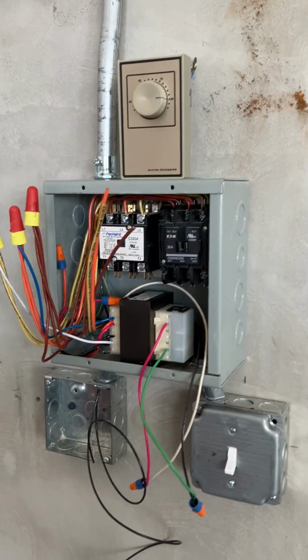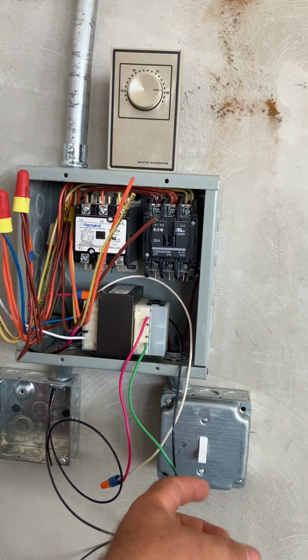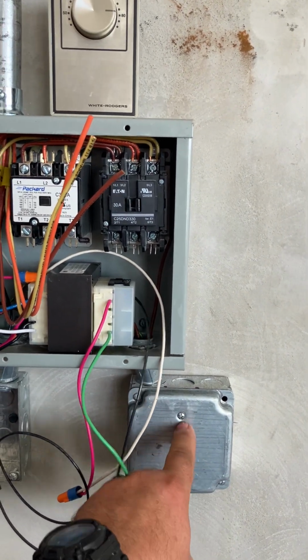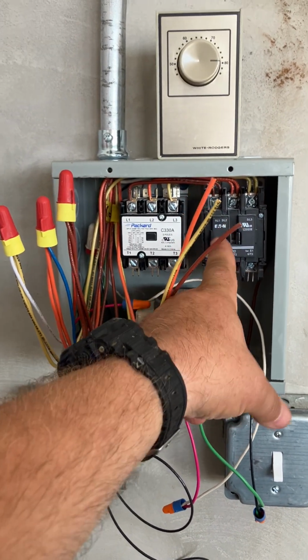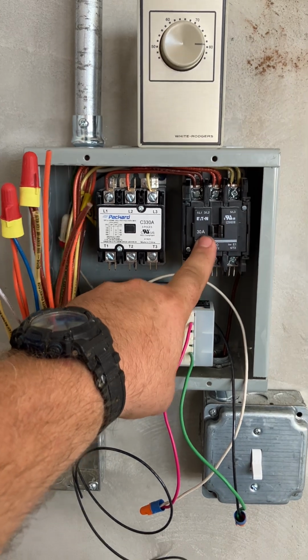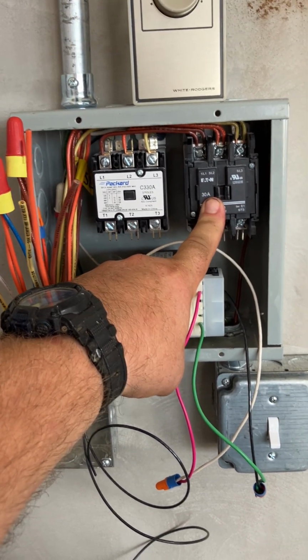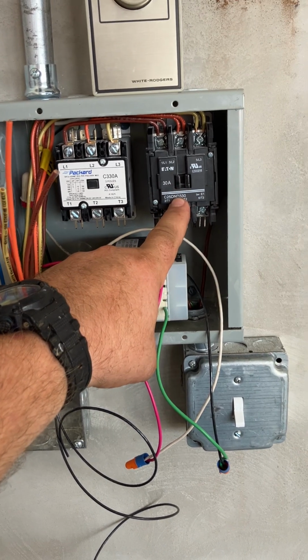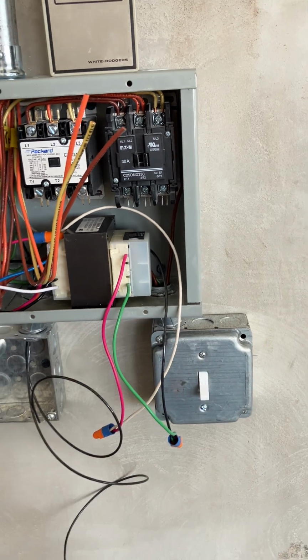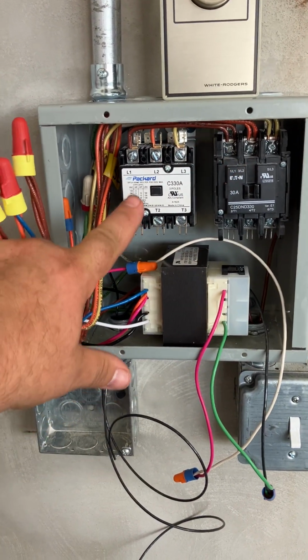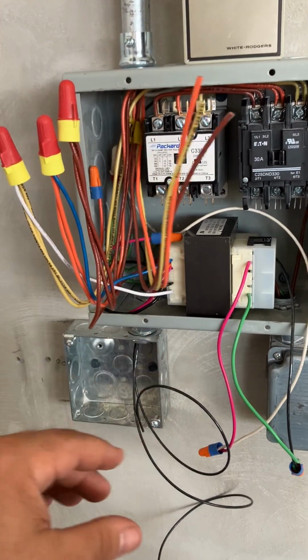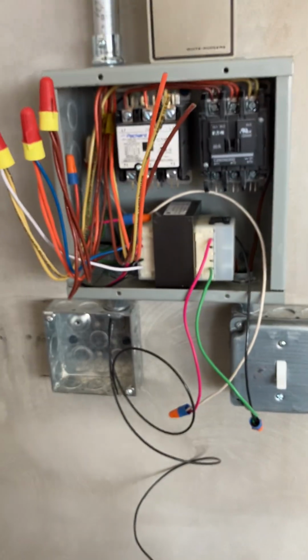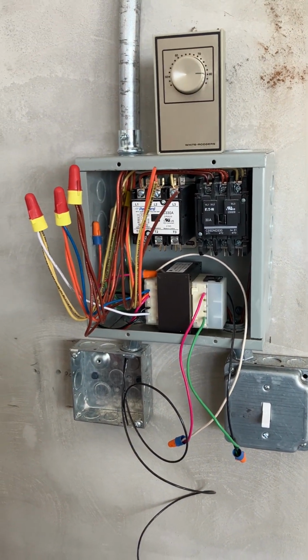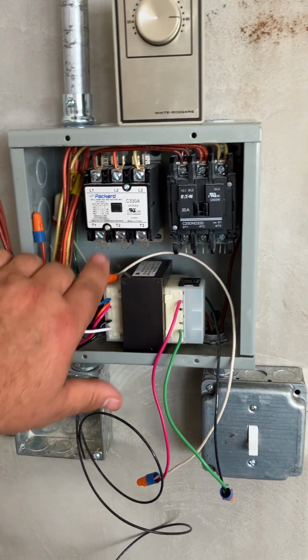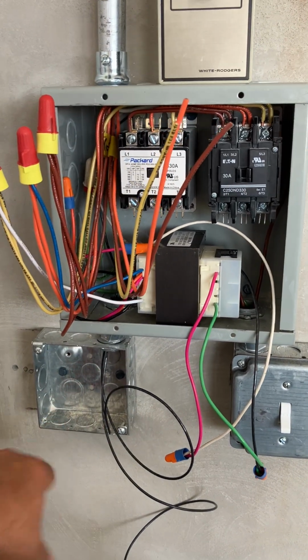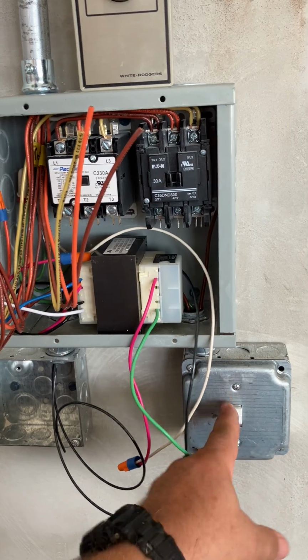Our original plan was to have a 277 volt rated toggle switch right here, so the customer could turn on the fans with a 3-pole contactor right here, 277 volt coil. Always look for the coil voltage because that matters quite a bit. 277 volt coil to be controlled from the 277 volt switch, and a 24 volt coil contactor, which was going to be controlled from this 24 volt thermostat, which the HVAC guy here kept promising me. And that's why we have here two contactors, one 24 volt coil to feed from the thermostat, one 277 volt coil to control from the toggle switch.